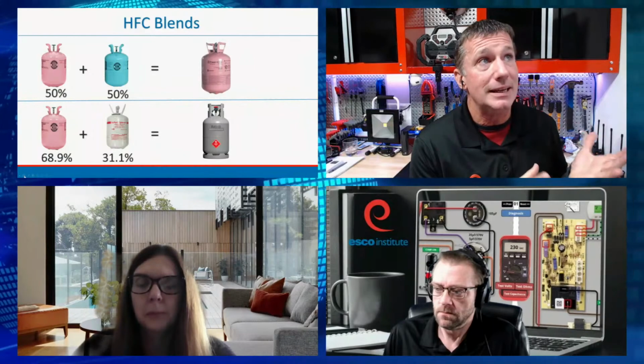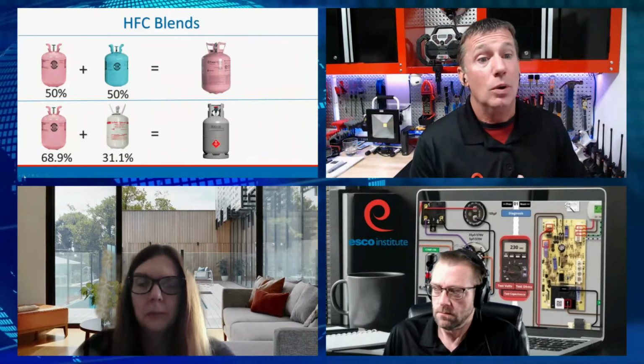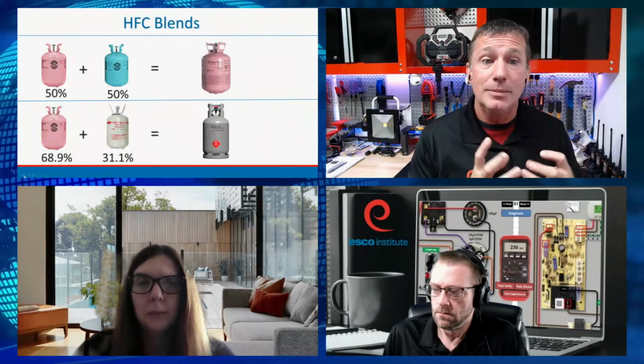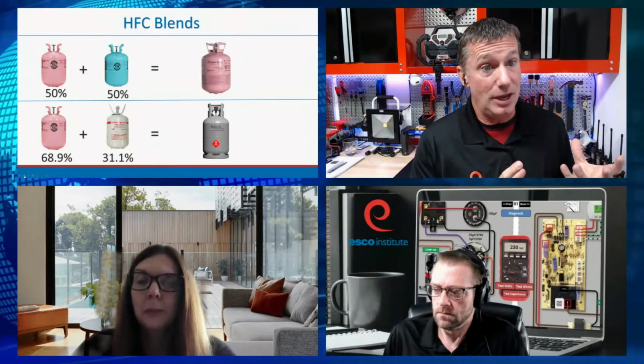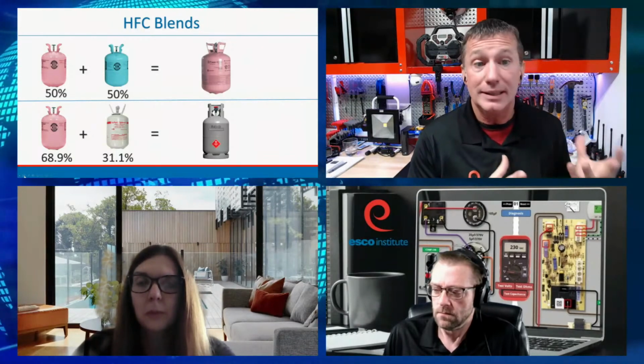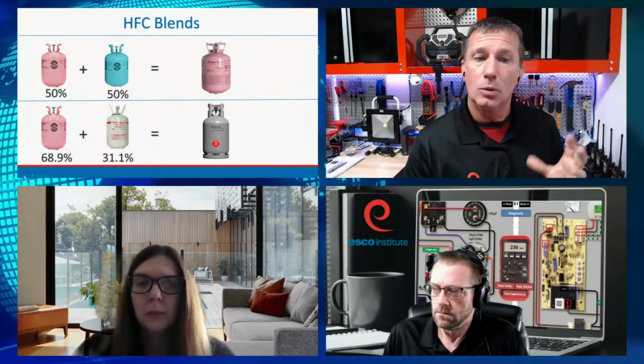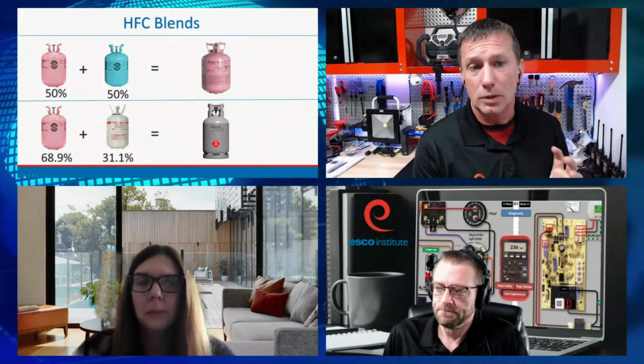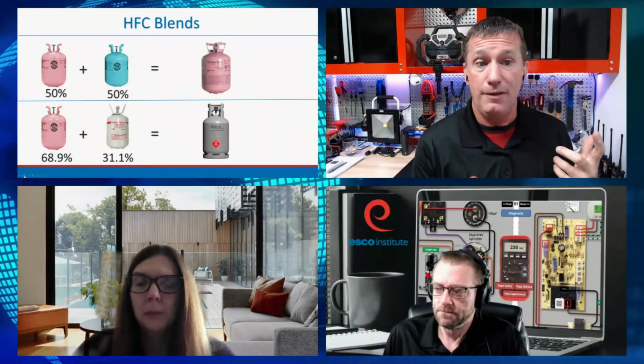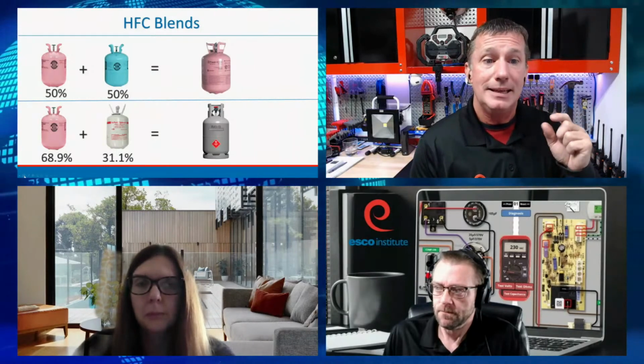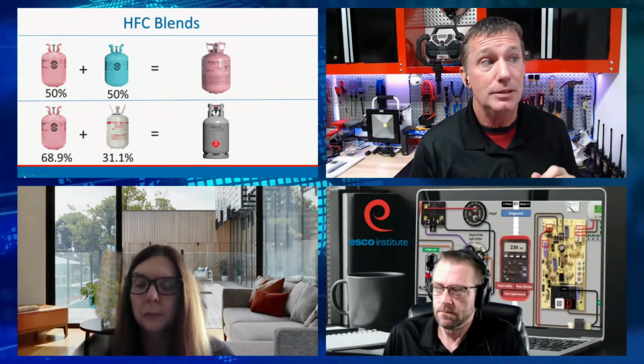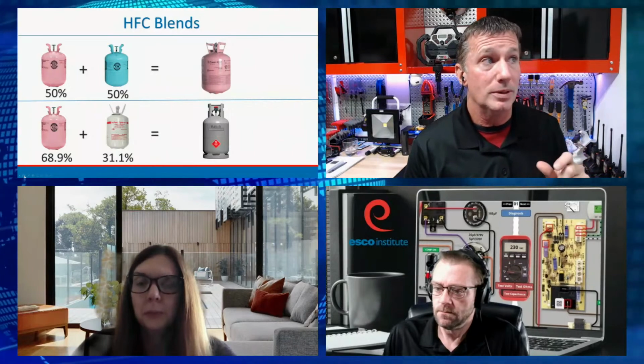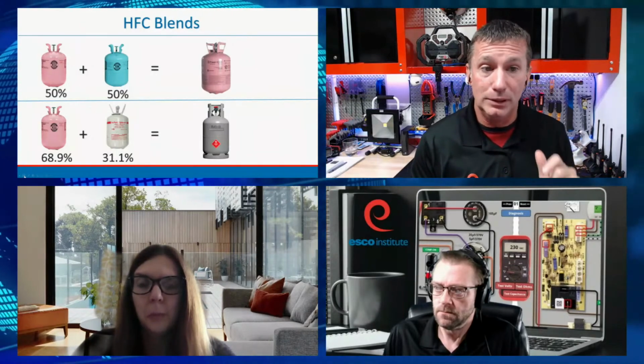We added R125 to alter the A2L back into an A1 category by reducing flammability. So we'll have things like R32 on its own, and we're also starting to blend these HFCs with HFOs, like the automotive industry uses with 1234YF. A popular one coming first of the year is R454B, which is a 68.9% R32 and 31.1% R1234YF blend.